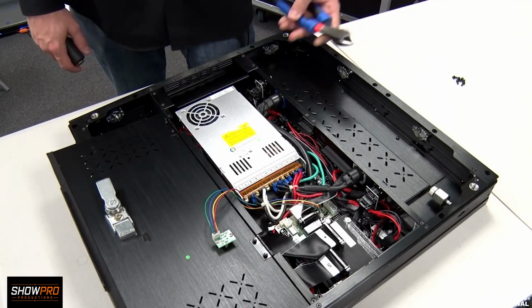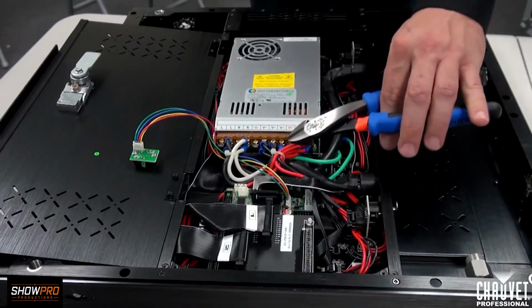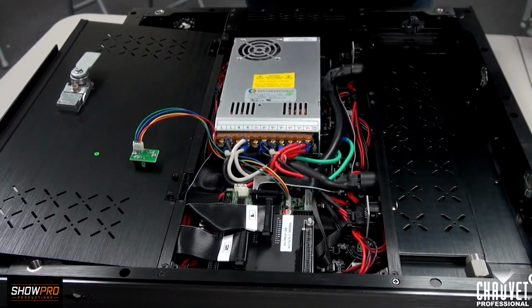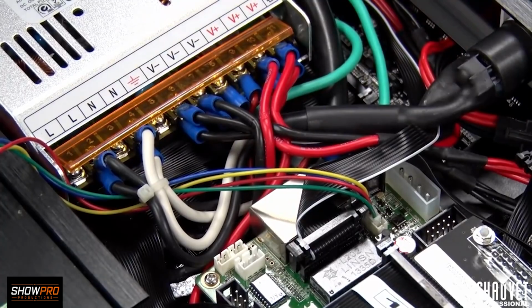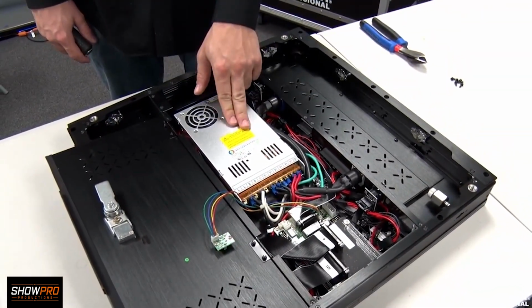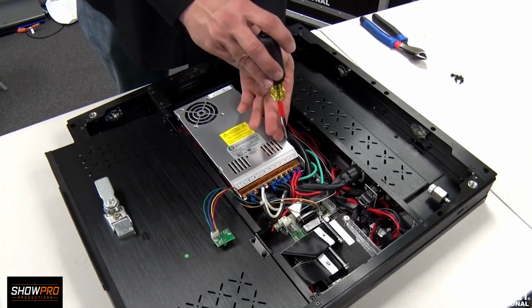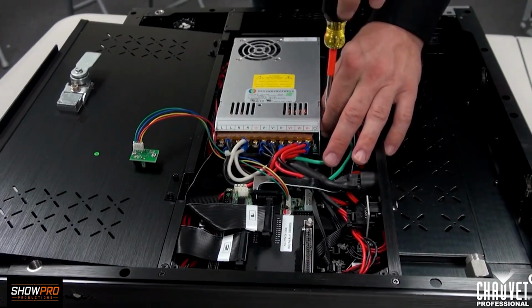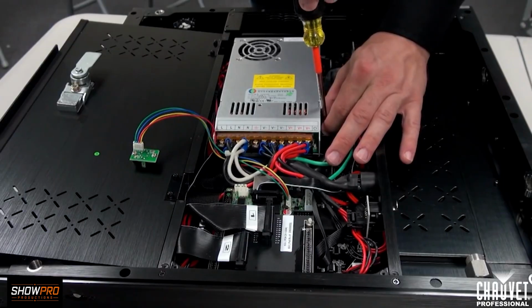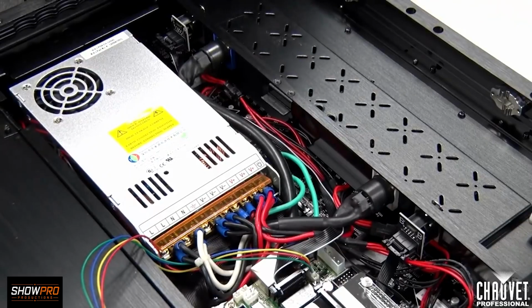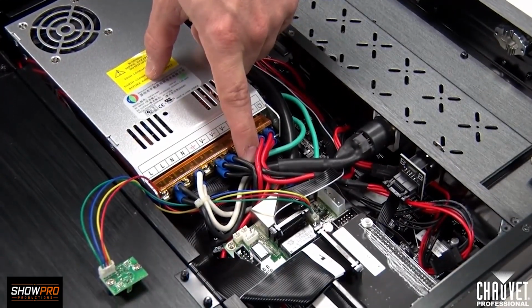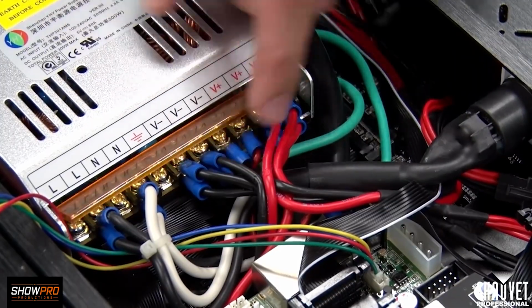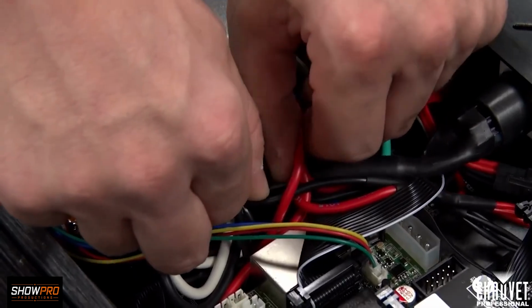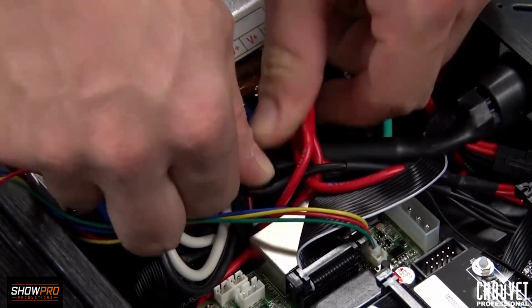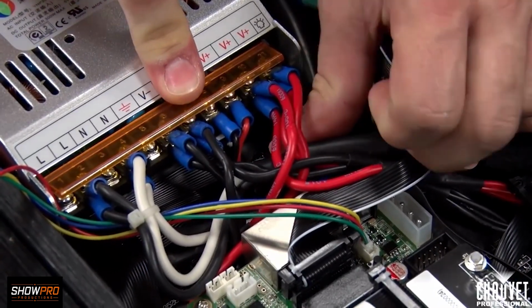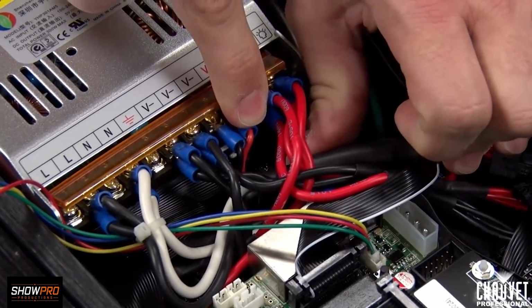To do this, we'll use our cutters to cut the tie wrap right here, being careful not to cut the cables, and removing it so it doesn't fall inside the panel. The power supply is held on with 2 screws—one on the side here, and the other located right behind this bundle of cables, so we want to be careful when accessing this. Carefully spread the cables with your hand, not using a metal tool. I've located the screw right here; it's difficult to see on camera, but I assure you it's there.